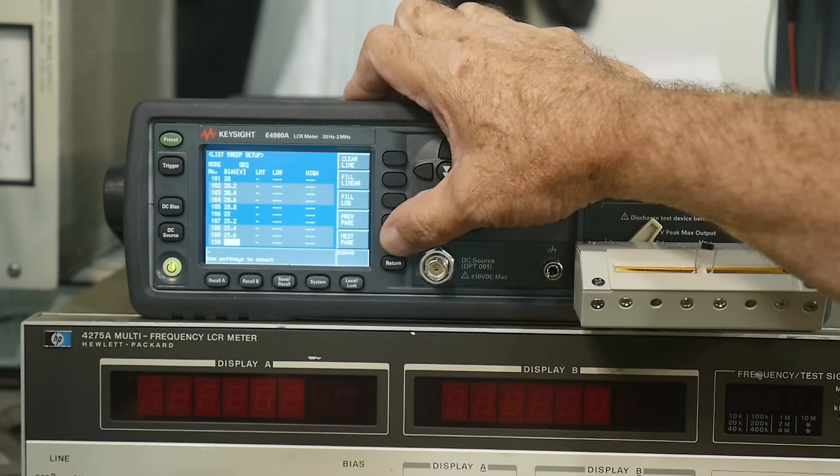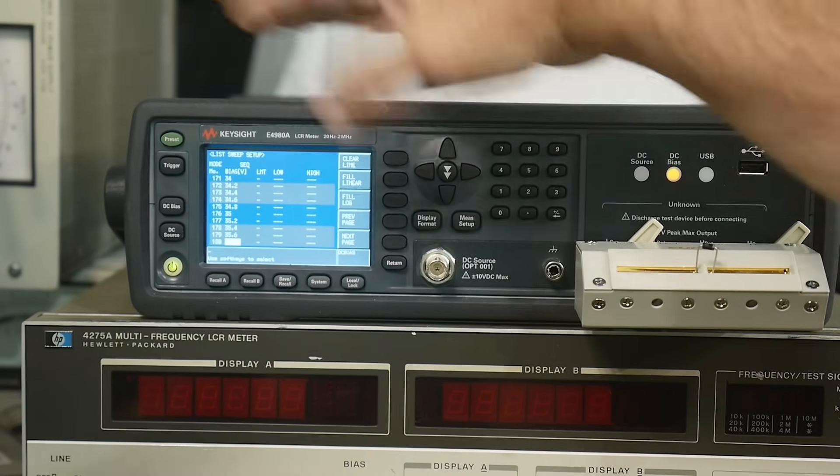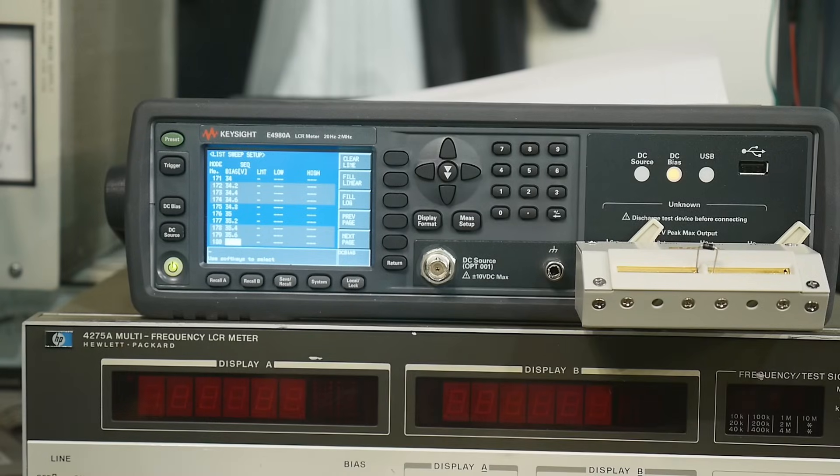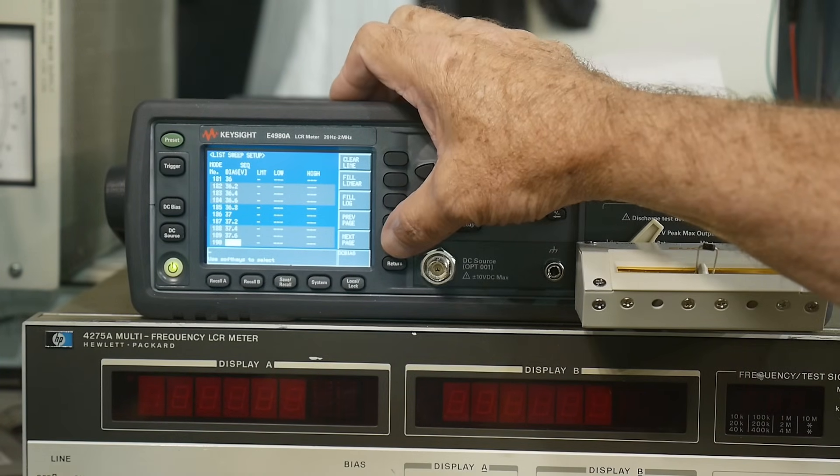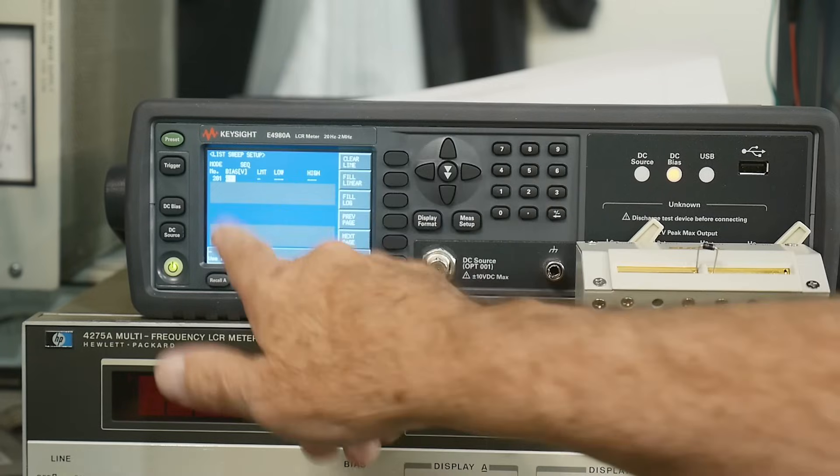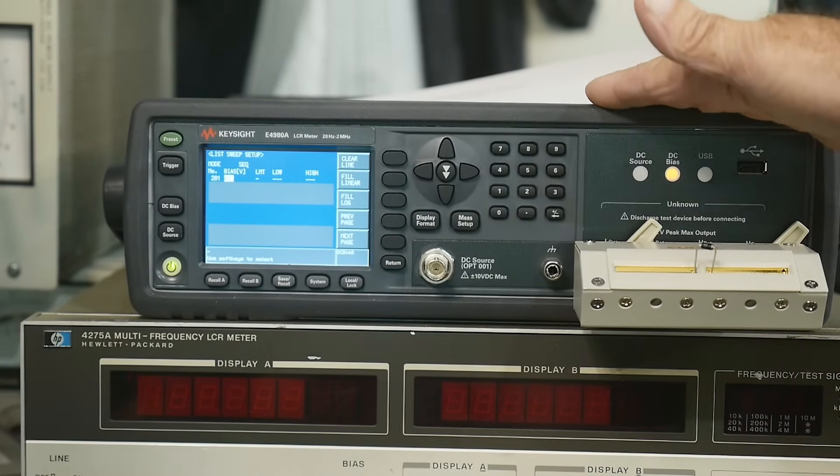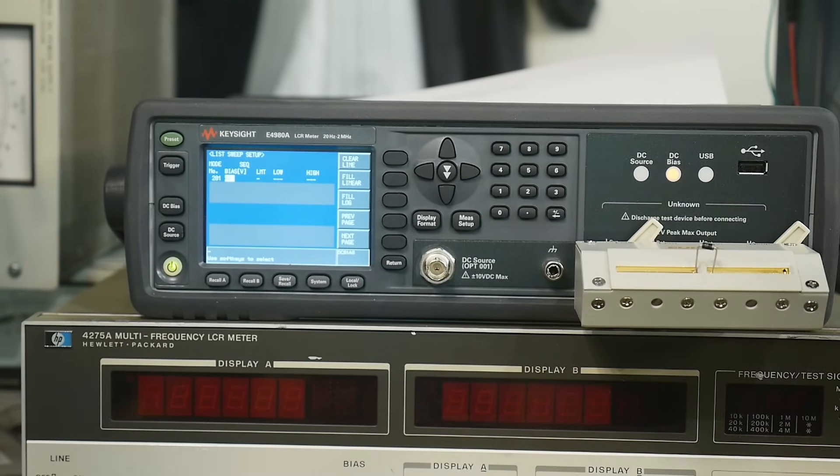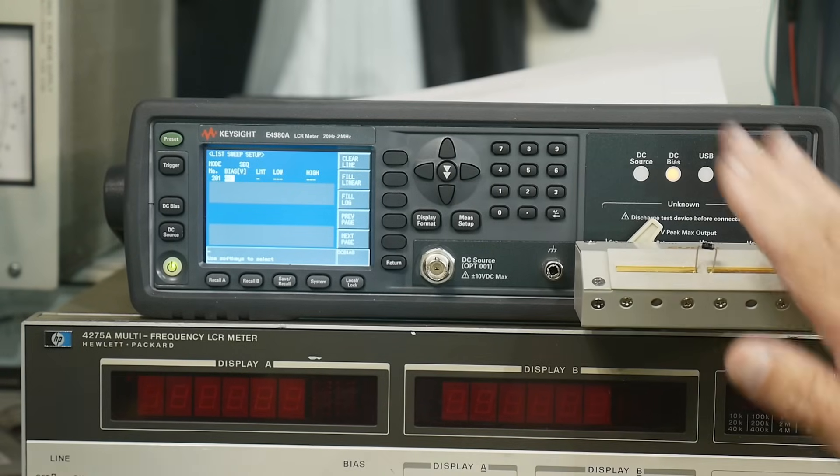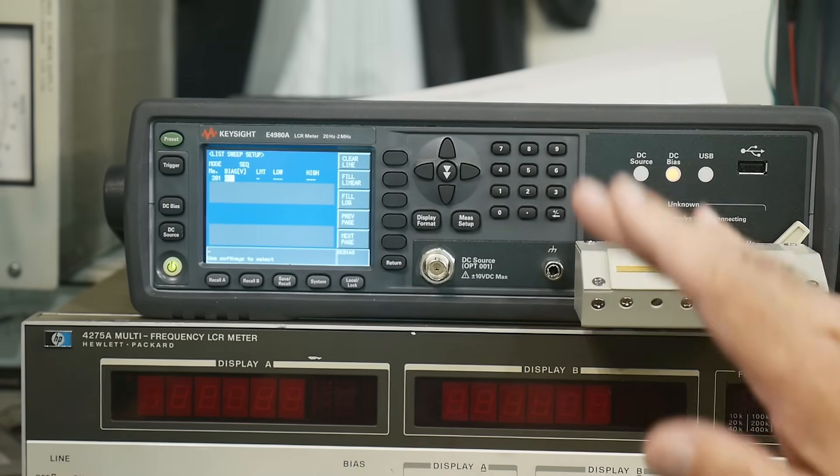So it's going to take those 201 points and it's going to take my starting point and it's just going to fill in the table. And so at 201, it stops at 40 volts. So that's the maximum capability of the machine, a 40 volt DC bias. So I'm going to sweep from zero volts to 40 volts automatically.